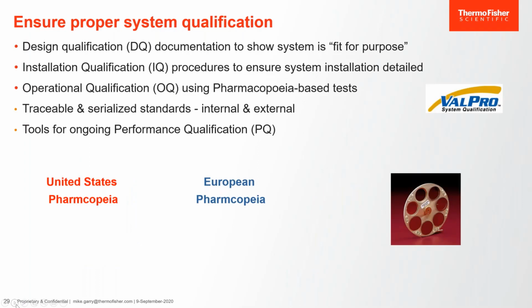In order to make sure that the system is properly qualified, a DQ is necessary, which is a design qualification. Most of our spectrometers are off-the-shelf spectrometers, but we do provide design qualification documentation to prove that the system is designed, which is fit for purpose.